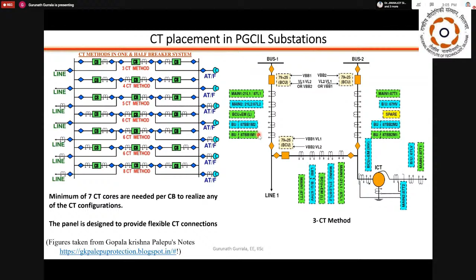So for this substation, we looked at all the configurations and the maximum number of CTs or CT connections needed. We decided to remove backup protection entirely, since for a lab substation you don't need backup, just main protection is enough. So we removed the main 2 requirements and only considered main 1, and looked at how many CBs are needed, all kept inside the substation. We used metering CTs of 0.2 class accuracy and protection CTs of PS class accuracy, so you can do protection and metering separately.